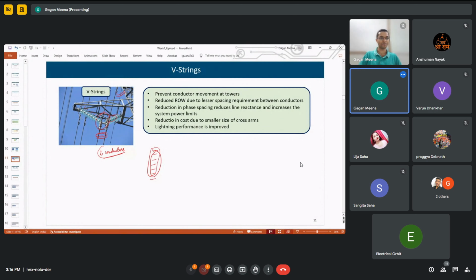One important thing is that if one of the units somehow gets damaged, we can replace it simply. And even if it is damaged, it can still provide insulation, and the conductor can still carry power, because it is modular. We can also increase the voltage level if the loading requirement increases, by adding more insulator units in that string. This is easy to do in this case, but not possible in pin type insulators.